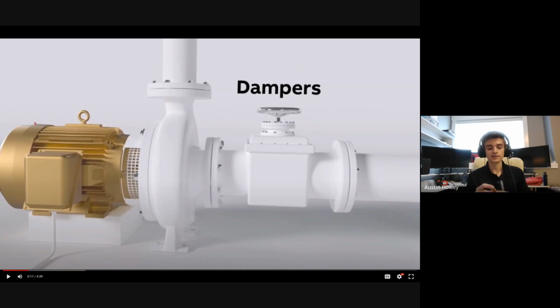Now, what's happening in a Bitcoin mining system, and I see this is the biggest problem, is that in this tube there is so much pressure on the back end that it's almost like a balloon. Instead of a tube with passive air flowing through it, your systems are almost like a balloon where this is closed off. If I put pressure through this, that pressure wants to come back into me, and it gets exerted on the sides of this tube. So that's a different analogy to look at this.